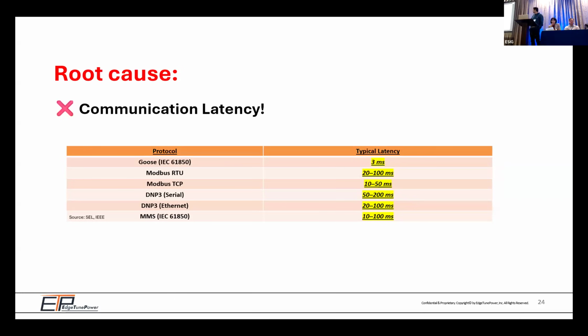Another point I want to emphasize, and you're probably going to hear a lot from me in the next 9 minutes, is communication latency. In offline simulation, again, I'm not here to say hardware in the loop is better, or PSCAD is good or bad. I look at PSCAD and PSS/E as a necessary condition, but not a sufficient condition, to make sure you capture all these communication latencies and discrepancies in the controller. You have to look at hardware in the loop testing. And I put this picture here intentionally to say that in any offline simulation package, you can also put a delay block to impose 50 millisecond or 100 millisecond.